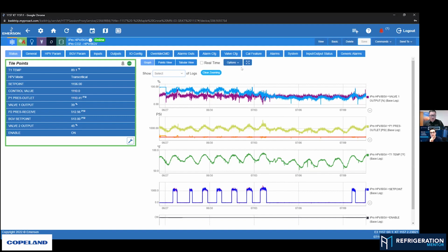I just noticed this one not long went transcritical too while we've been talking here up in Minnesota. So what it did there was it transitioned from a subcooling set point to a pressure set point. So now we're starting to lose our temperature and pressure relationship because we're above the critical point of CO2. So now it's just trying to maintain a static pressure set point converted from the temperature sensor. Just take out as much heat as we can now from the gas cooler through the valve, still create a pressure drop and get usable liquid.